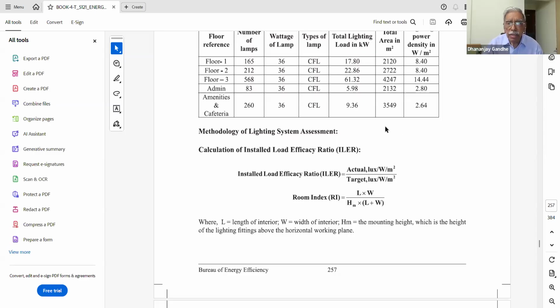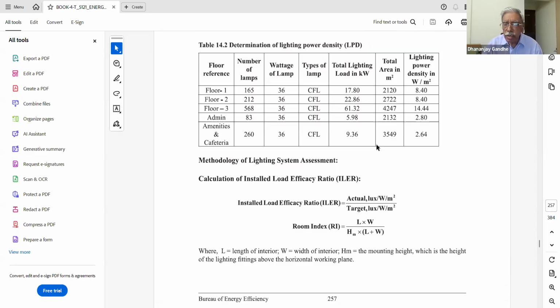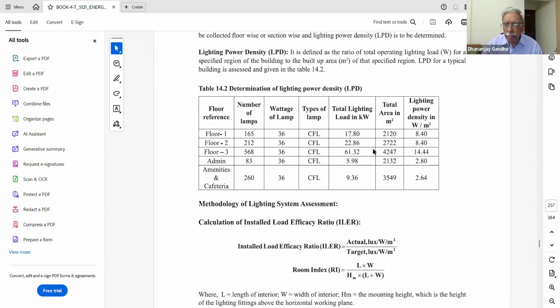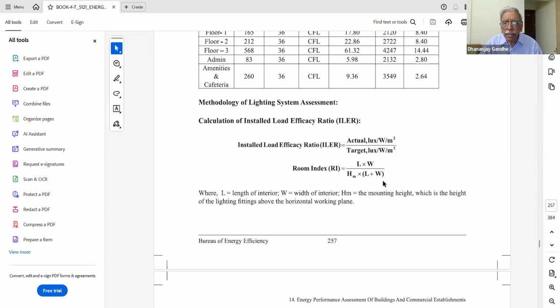So this is calculating the lighting power density, and then these figures can be tallied and compared with the design figures which were taken for the lighting design, and that is the first exercise. Then, in order to assess the efficiency of the lighting system, that means the actual lux obtained by a particular lighting design, the number of lamps, etc., and what is the target lux density when the design was done. So the ratio of actual lux, that means actual illumination density, divided by the target, that means the design illumination density.